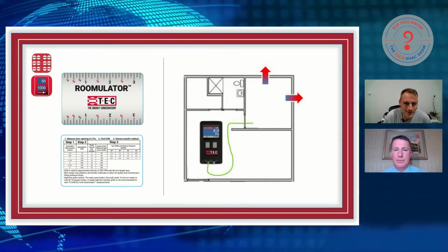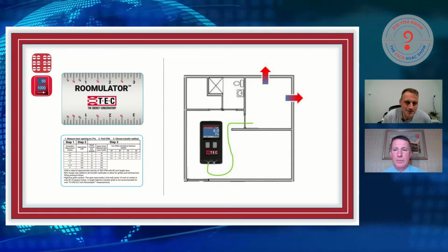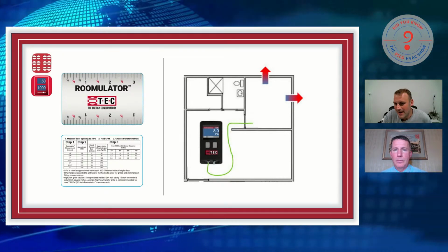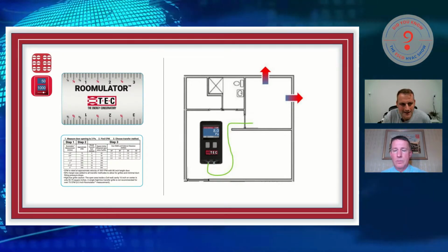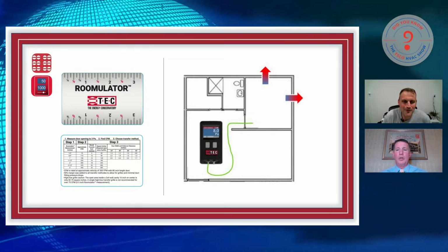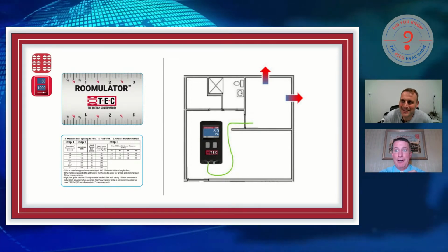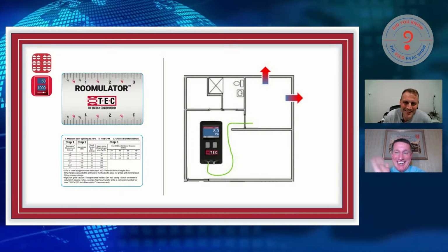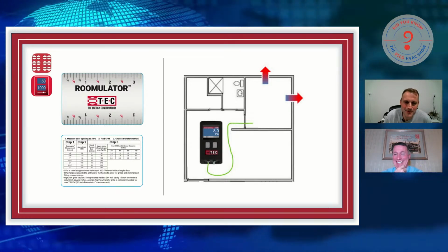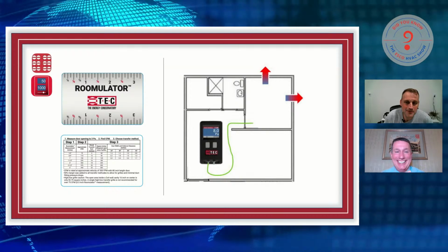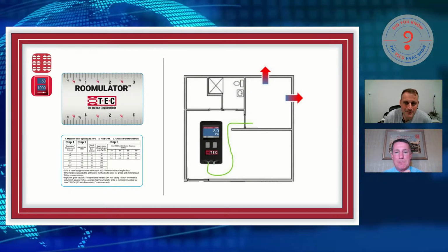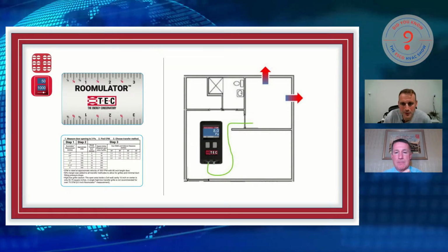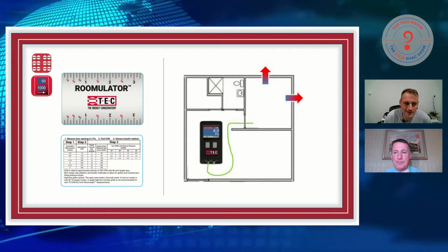Here's what I'll tell you. I didn't want people searching for K factors of grills or anything like that. This needs to be something quick and easy. A friend of mine would say, keep it simple, stupid. So that's exactly what we did. There's 50% margin built in for a 90, 2 grills, 1 on each side. All that's built into the measurement.